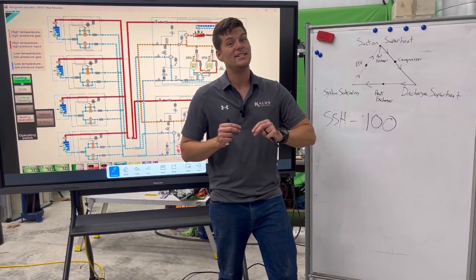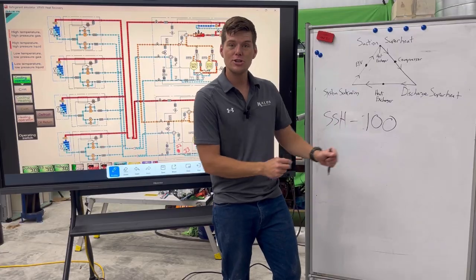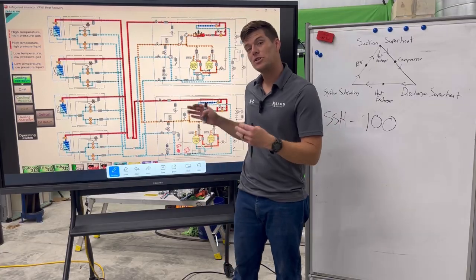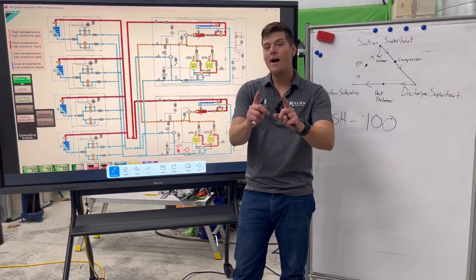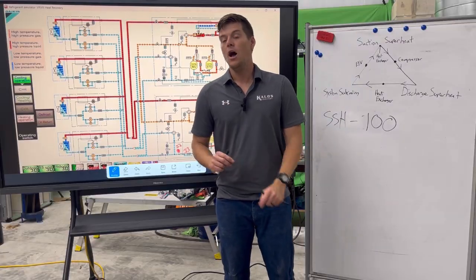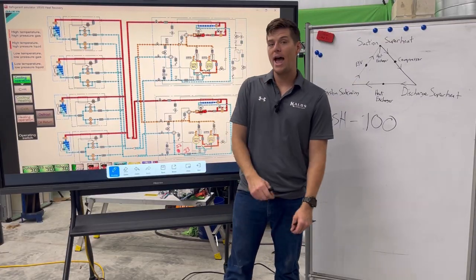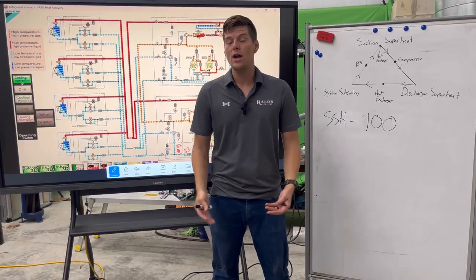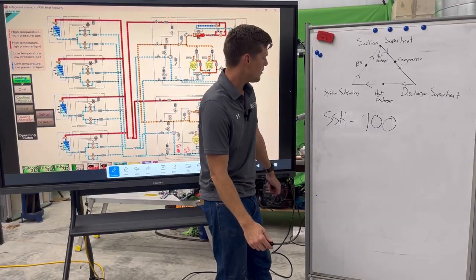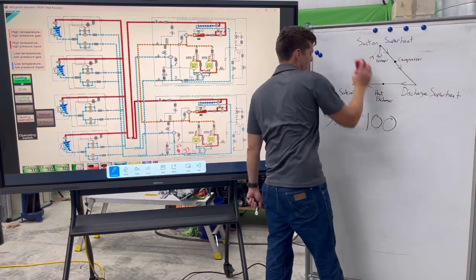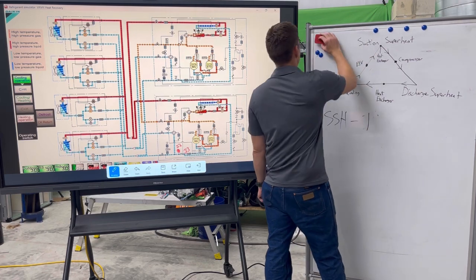Every compressor has a different health range for discharge superheat. So you can't just take the numbers that I'm showing you here and apply them anywhere. However, the concept is universal. Understanding what vapor pump I have and what it's designed to do is the whole premise of this conversation in the first place. So let's go back to 1 degree suction saturation, right?